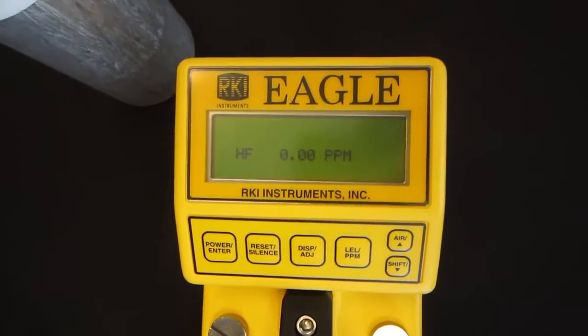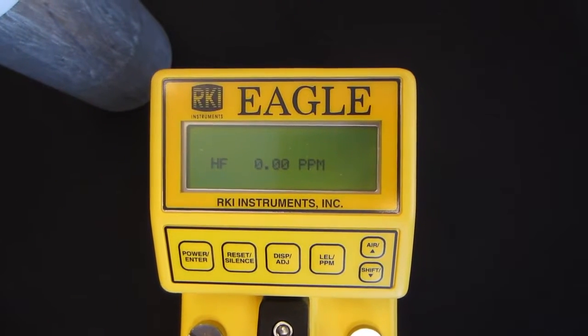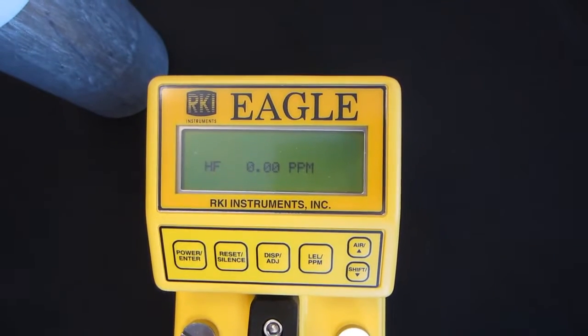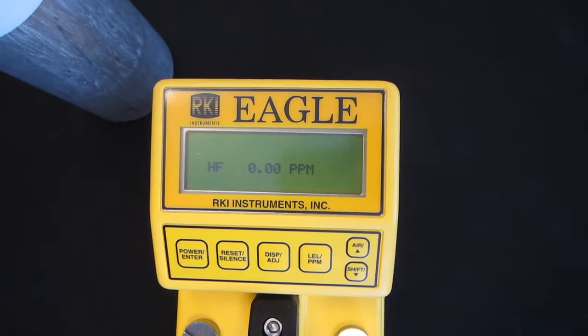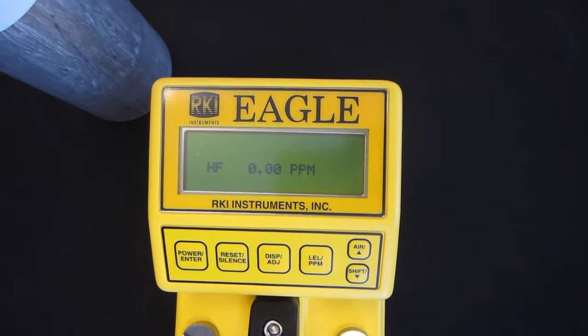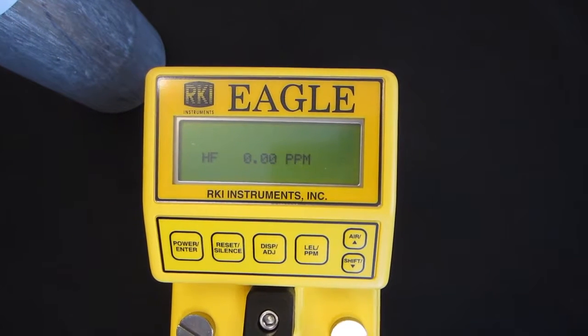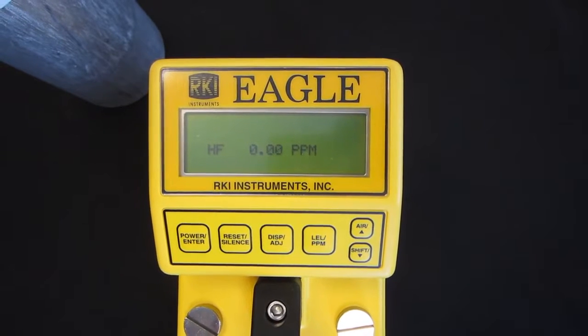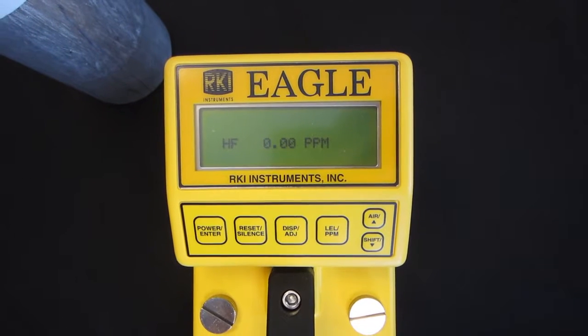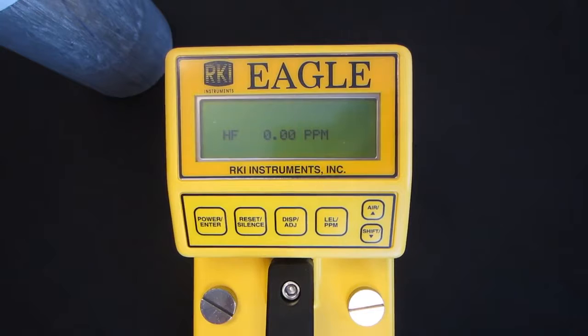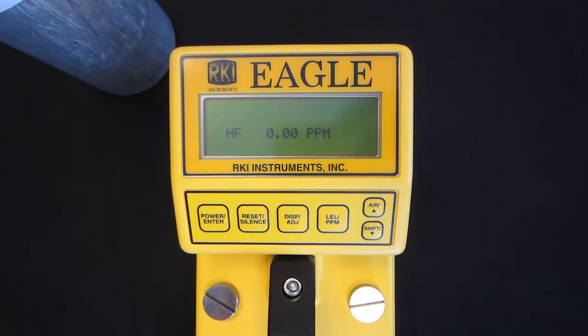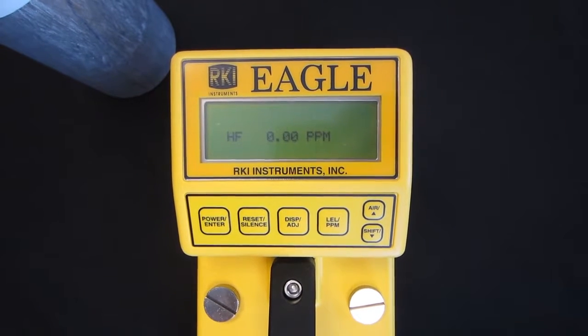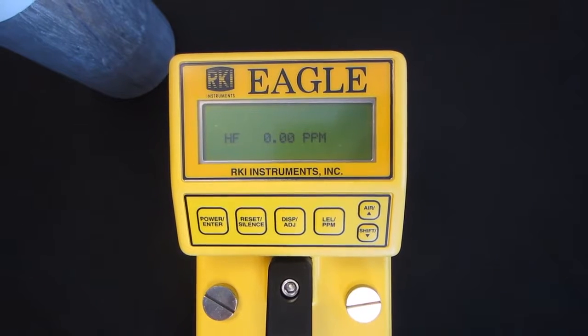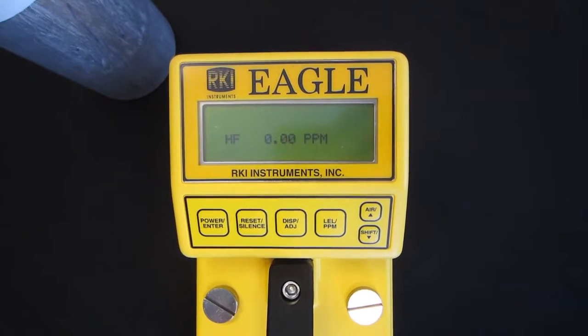We're just going to show you how to do a bump test, which is very easy to do and simply involves applying the gas to the unit while the unit is in normal operation. The Eagle does not have a formal bump test mode, so don't worry about going into a special bump test mode to do a bump test. Really, you're just simply applying gas to the unit while it's in normal operation like it is now, and then just observe the readings.